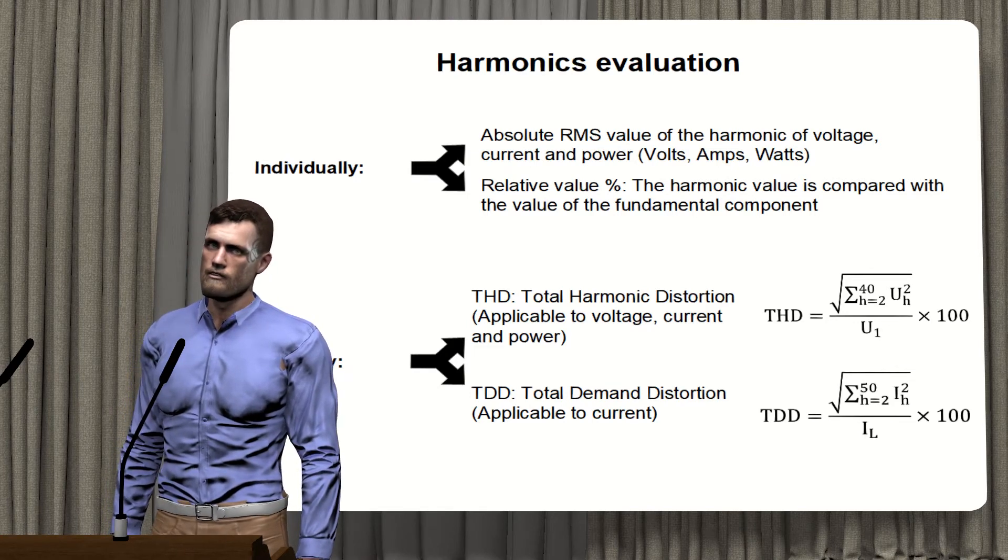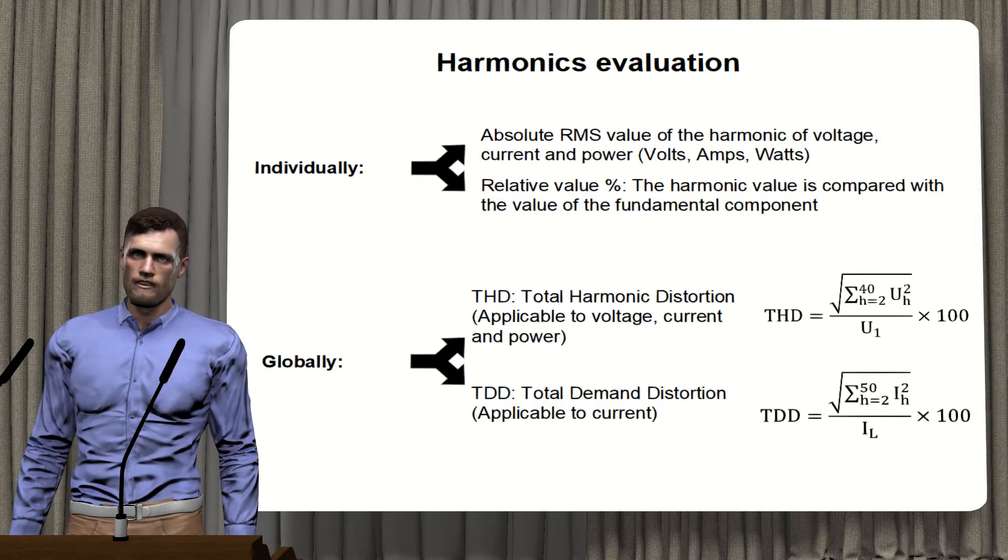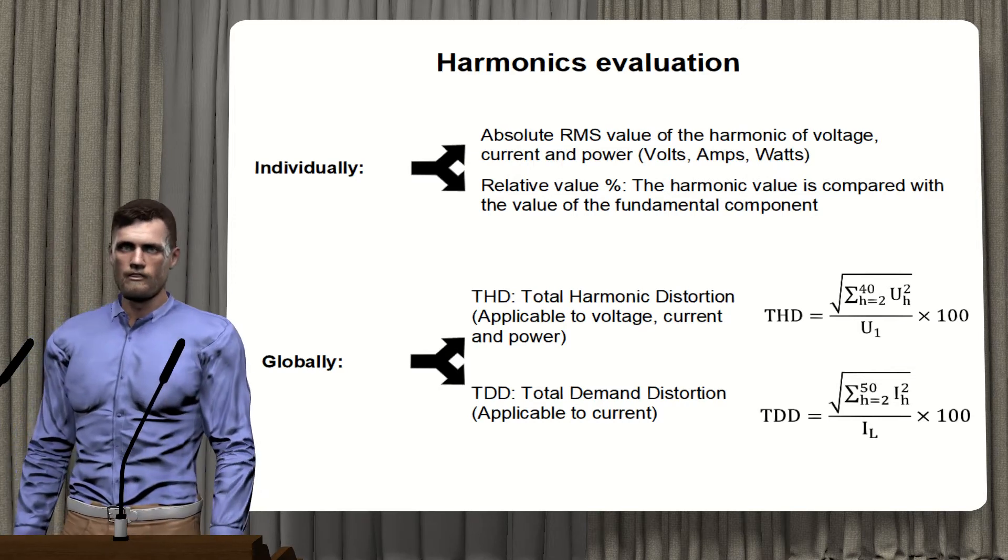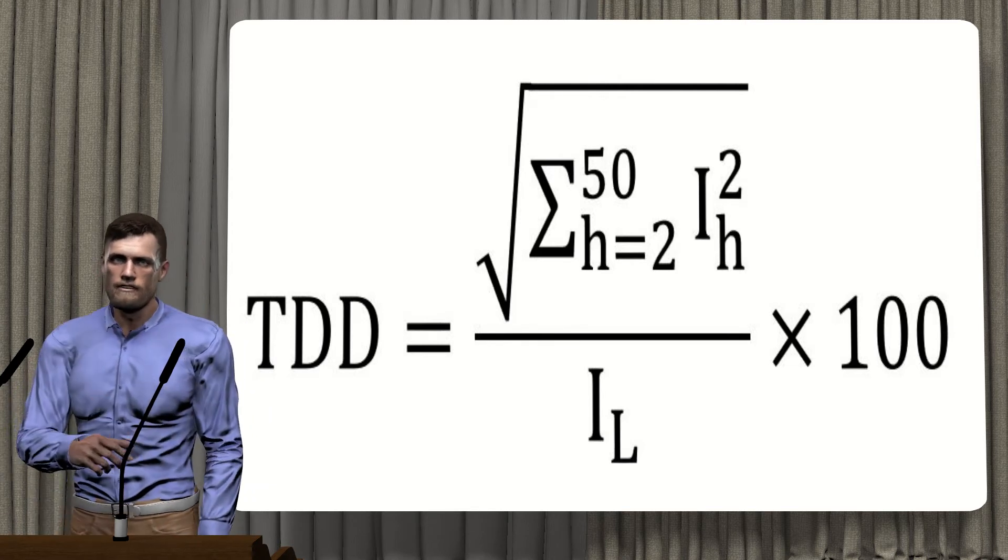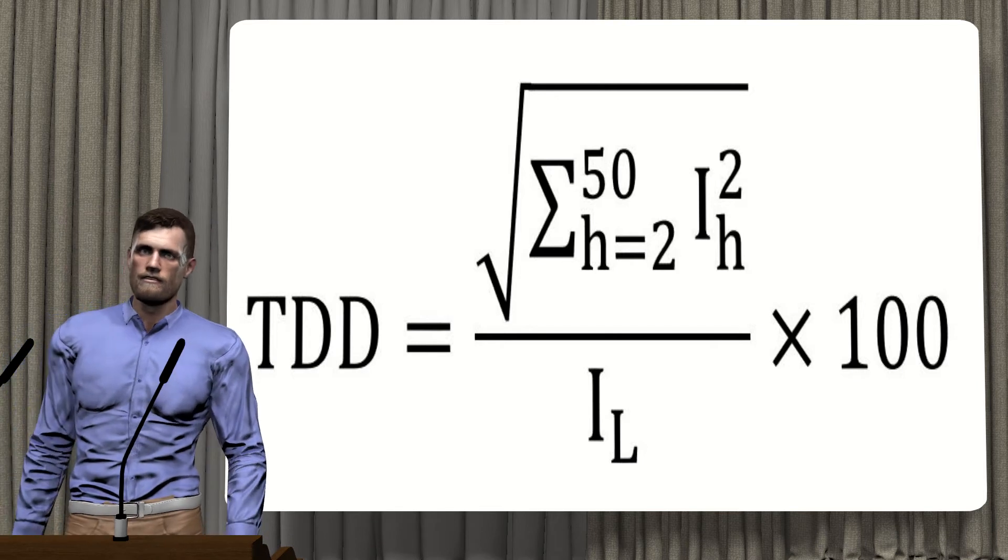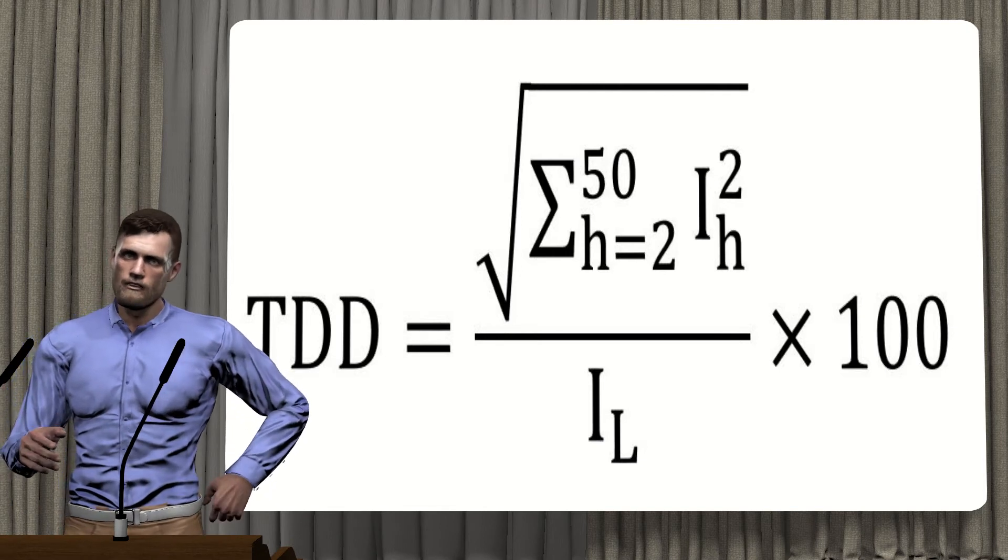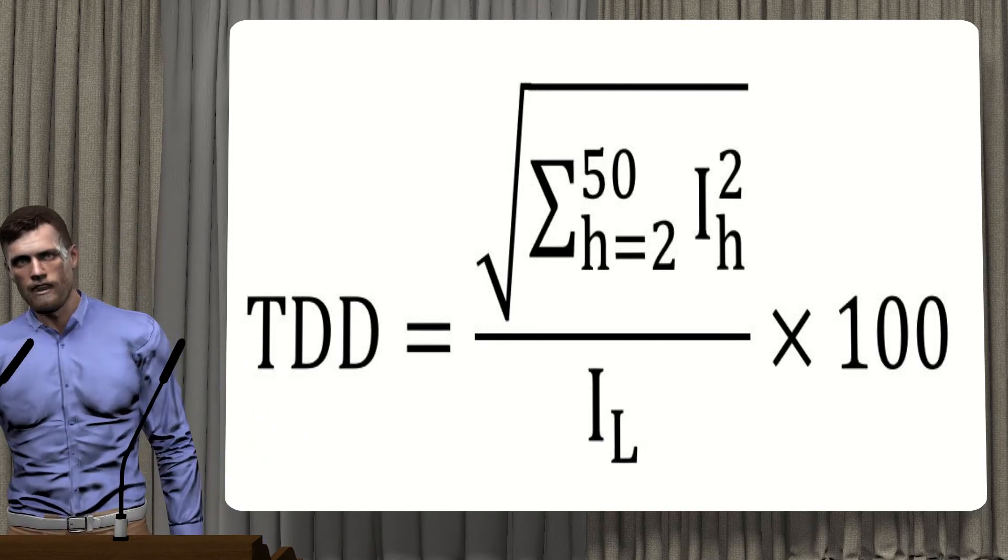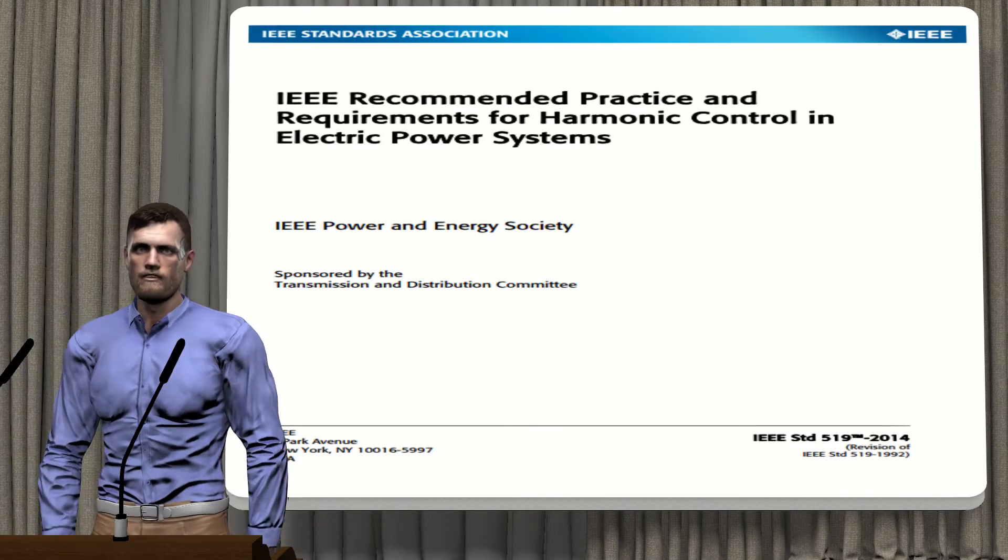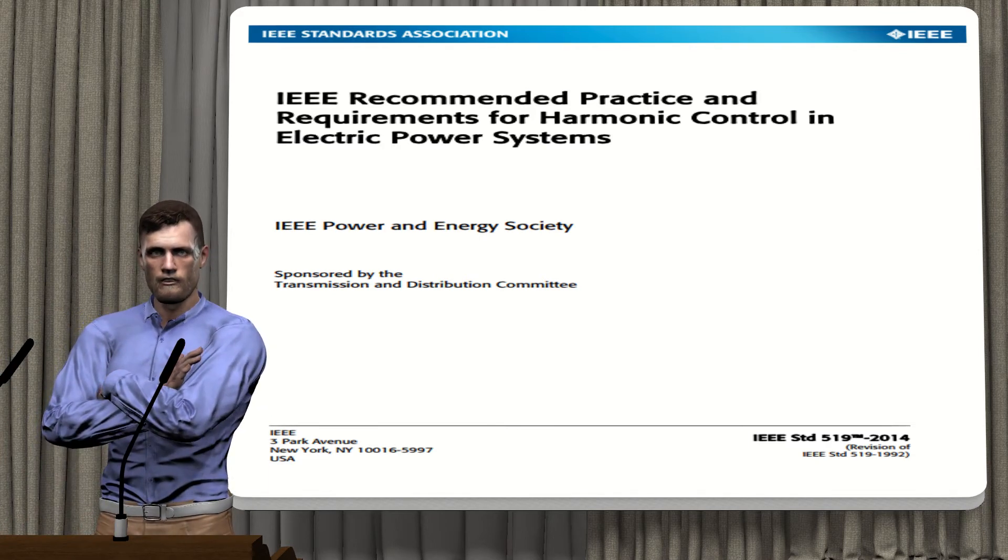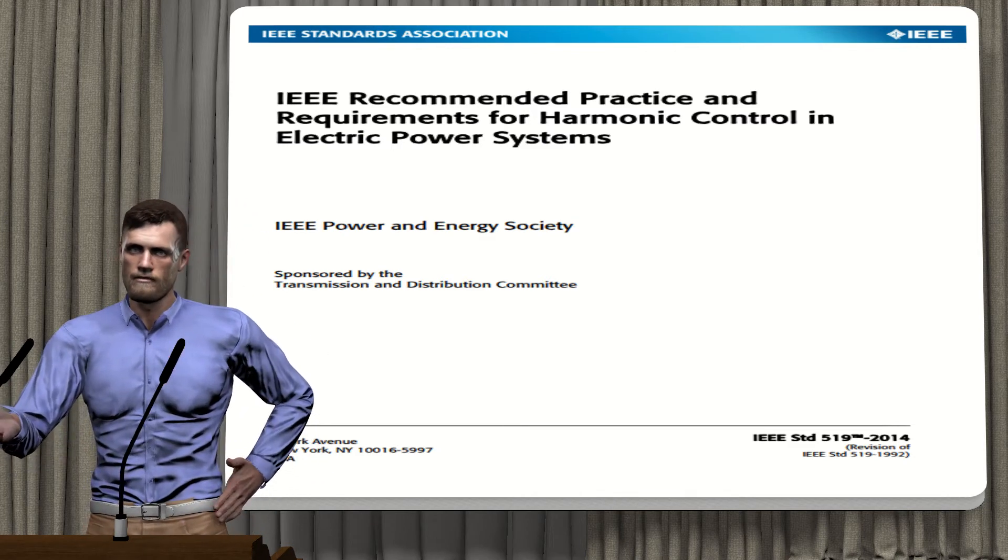The formula for TDD is similar to that of THD, but if we look at the denominator, we will see that now the parameter IL appears, which is the maximum current demanded. In this way we are comparing the impact of current harmonics in relation to the maximum current of the installation, which will give us a better vision of the load level that harmonics represent. The standard EN 50160 is applicable only to the quality of the voltage, so it does not establish limits regarding harmonic contamination in current. In this case we can use the IEEE 519 standard, which does establish a limit to the TDD value, depending on the value we obtain for our installation of dividing the maximum short circuit current by the maximum current demand, as we can see in the picture.